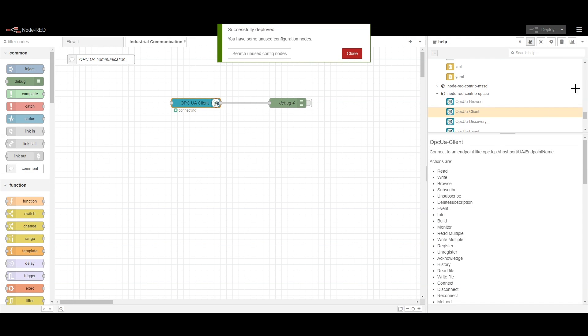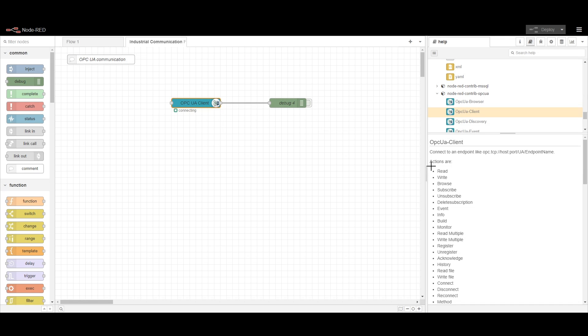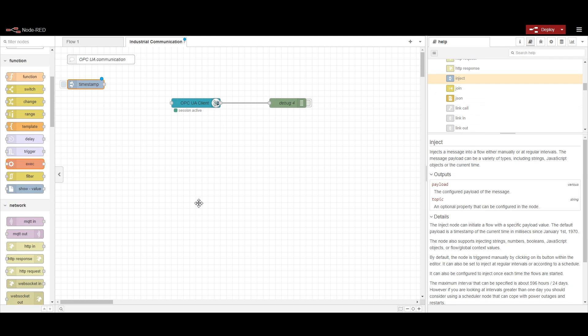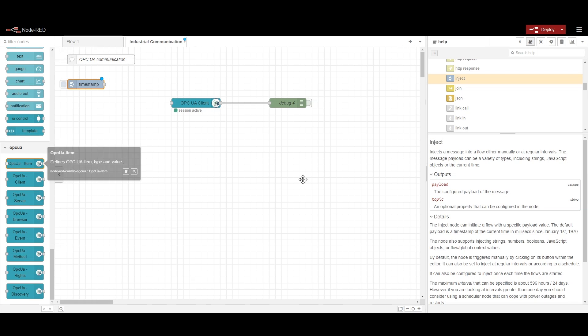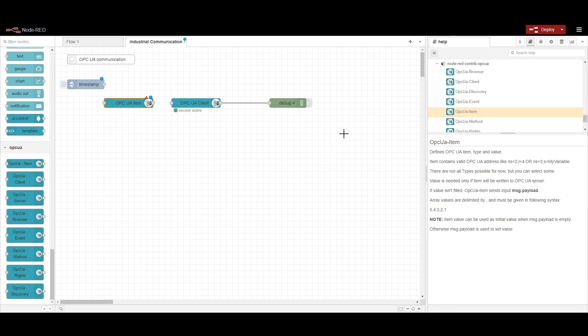Once it is deployed, let's see — it is going into connecting mode, and then session is active. So the session has been created. Now the next step is to read data from the PLC. Let's find the OPC UA item node — we will drag and drop the OPC UA item node where we need to configure the node address to read data from the OPC UA server. Here we need to provide the item details; the node data is basically the node ID.